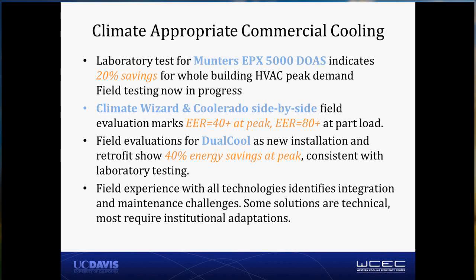I'll talk about a side-by-side field evaluation that we've run with Walmart in Southern California to evaluate and compare the Climate Wizard and the Coolerado. It's been exciting to have a side-by-side comparison. Both of those equipment are marking really outstanding performance. At peak, we're measuring energy efficiency ratio better than 40, and at part load, we're measuring energy efficiency ratios that are better than 80. It's really impressive. Both of these equipment I'll talk about later, but they're applied to cover the ventilation requirements for the space, and they do still rely on some of the other rooftop packaged air conditioners to provide for some of the room cooling load during peak conditions.